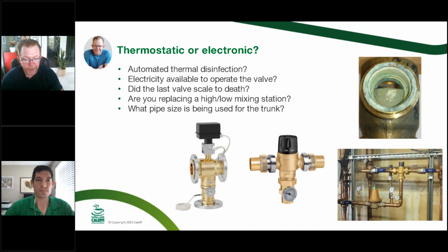And while that electronic one that Max is trying to sell is more money than the thermostatic, again, if you've got scale issues, keep that in mind. It could be more money up front, but long-term savings on the project. The other thing we've got to keep in mind, and we're going to talk about this, is that whole high and low flow situation. We have to make sure that whatever we're doing, we're not just designed for peak flow.